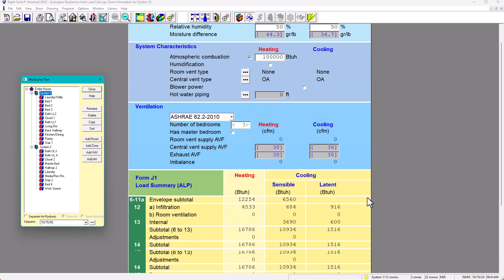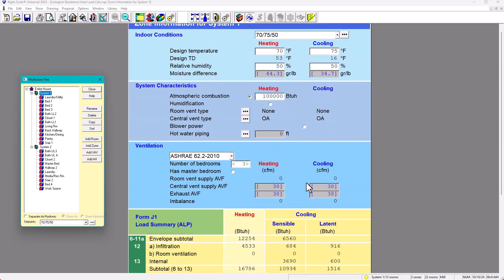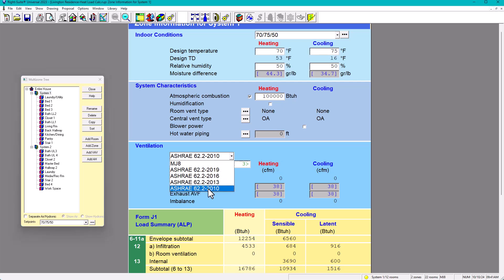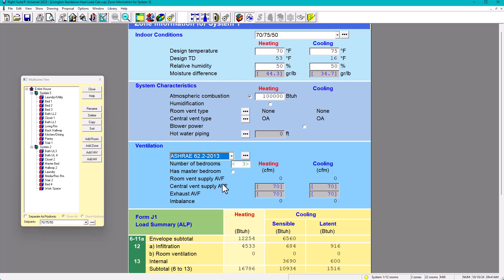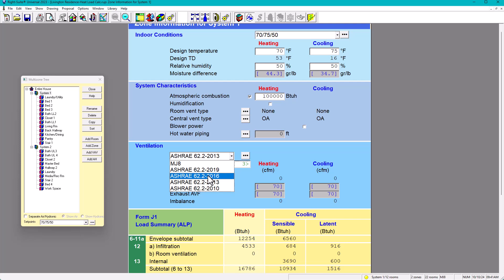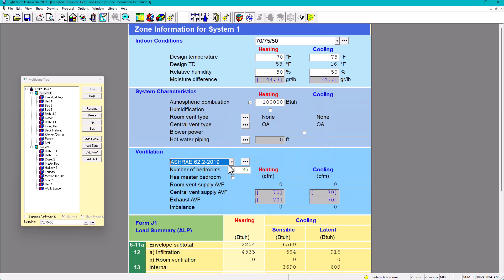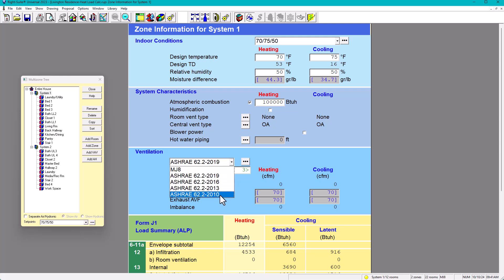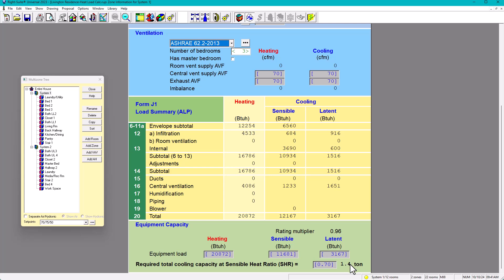For System 1, the tonnage is 1.3 tons. To be on the safe side, I prefer ASHRAE 62.2 2013 over 2010 — it gives significantly more CFM and bumps the load to about 1.4 tons. Testing 2016 and 2019 shows similar results. I recommend using at least the 2013 standard because it gives more ventilation and increases your load slightly, which helps you stay in the safe zone.